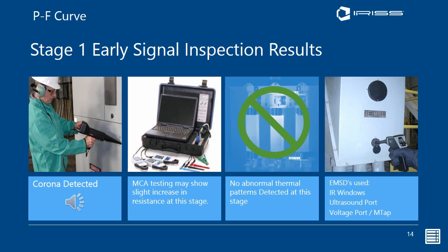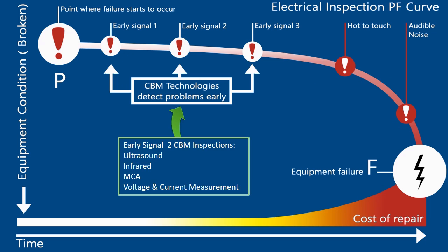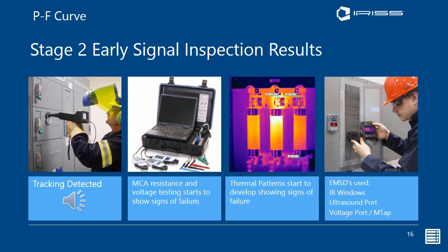The second stage, you may start to hear tracking, and tracking sounds like this. Very distinctive. Some people relate it to popcorn. Now, your voltage and current measurements start to show significant signs of degrading, and your trend plots will go up. And the thermal patterns at this stage, we should start to see some significant heating around the failure points. Again, EMSDs will be used: infrared windows, ultrasound ports and voltage ports.